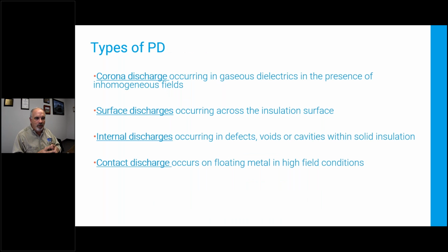I'm going to talk about 4 different kinds of discharge. Corona discharge is the most common, the least dangerous, and lots of people use PD and Corona interchangeably. They're not. All Corona is PD, not all PD is Corona, to coin a phrase. So Corona is a form of discharge where the insulation that we are discharging across is gas, typically air. And so when I've got an EHV line and I've got a sharp point on a piece of buswork up in the air, I exceed the withstand capability of the atmosphere right around it. So those air molecules break down. They break down to the component parts of oxygen and nitrogen and that, but it's a discharge. The current flows out into the air.